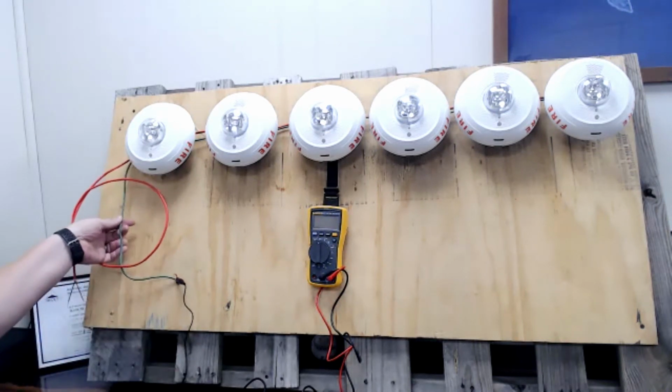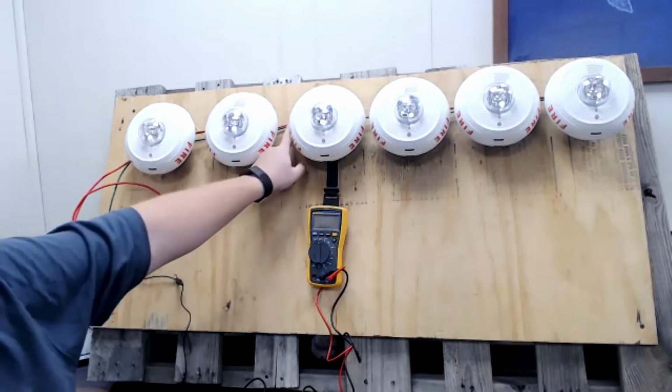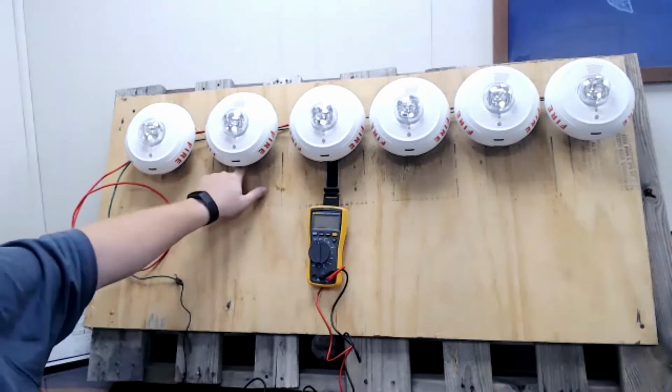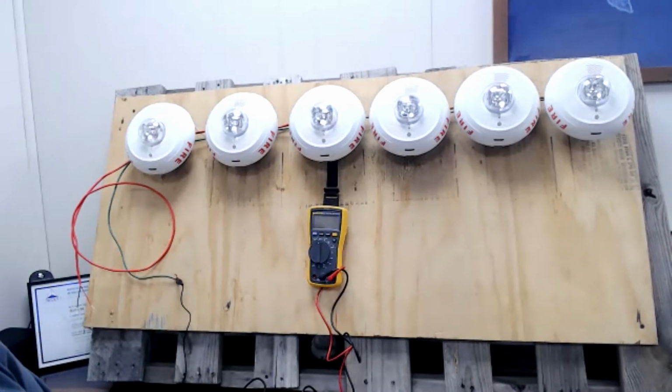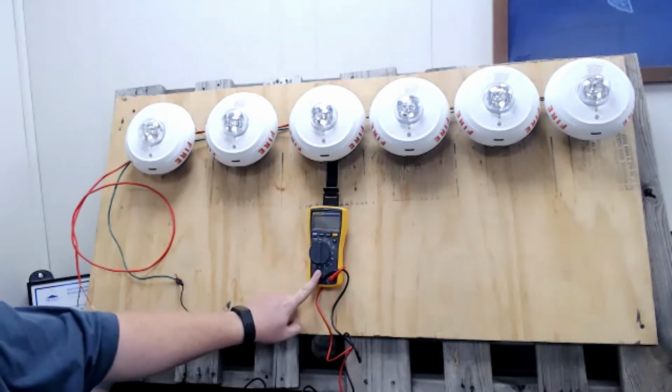So I used this green wire you can see over here, and you can kind of see it between the devices. I had to connect each box that these are mounted to so that I could create a ground. Because what I've done with my 6 devices here is I've made a small little NAC circuit of just strobes and horn strobes. And I created a few problems like what we've been talking about. In one of the devices, we're going to find an open circuit. Another device, we're going to find a reverse polarity, like it was wired backwards. And in a third problem, we're going to find one of the devices has a ground fault in it. And the point of what we're doing today is we're going to learn how to find all those using our meters, not our panels.